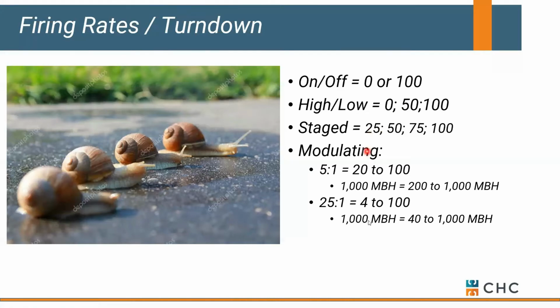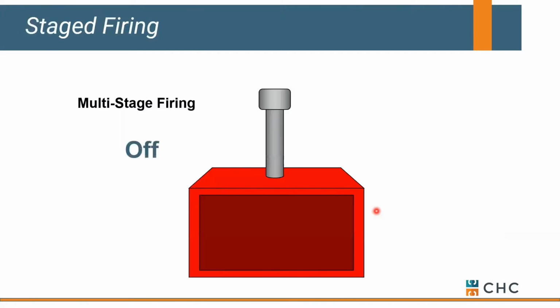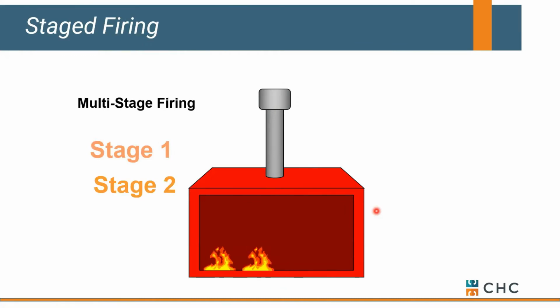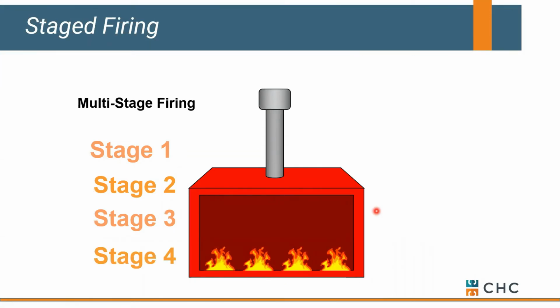More commonly though, we're seeing a lot of boilers out there that are set up with a modulating design. Kind of like having a pump on a VFD, it allows that burner to modulate to track system load. So that's typically what we're seeing these days is a modulating burner. So just some quick examples. Stage firing, again, there might be 4 gas trains and you could bring these on as needed. It works very similar to your barbecue. If you need more heat, you're going to either crank it up or bring on another section of your burners. Okay, you're doing the same thing with this boiler.